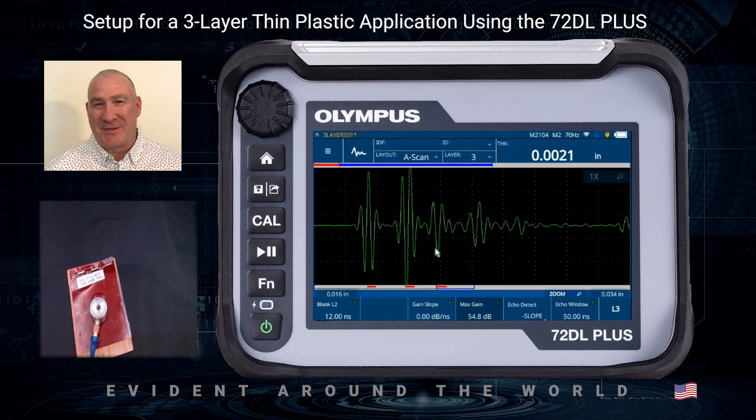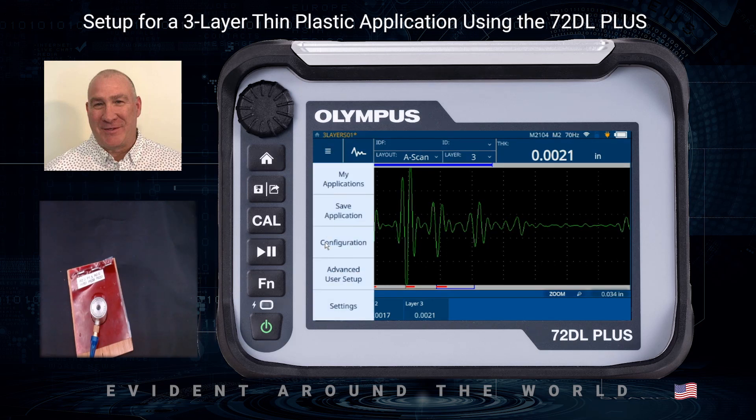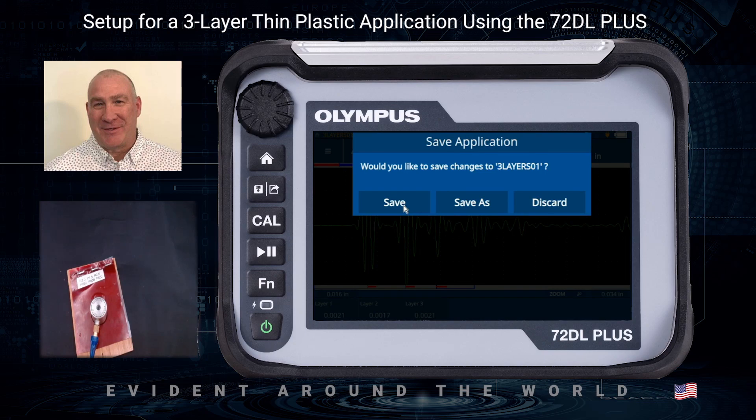We have a three-layer material with the surface echo, reflection off the first layer, the second layer, and the third layer. Going out of Wave Adjust mode, I can look at my measurements: the first layer was supposed to be two mils thick, the second was 1.5 — pretty close — and the third is two. Very clean echoes and proper detection.